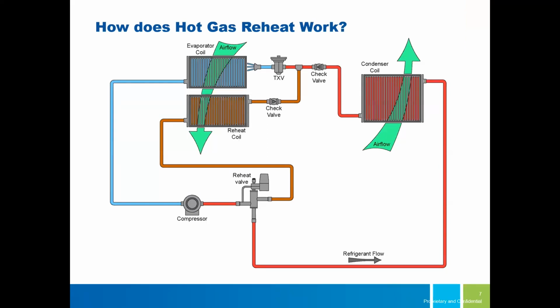For smaller package units, there are different styles of reheat. They have on/off, so it's basically one size coil. Generally speaking, for smaller package units, you see air coming in reheat mode usually off of 70-degree neutral air, or some type of dry neutral air that comes off of it in some way, shape, or form. And I could be wrong. We're getting into the applications realm, which is a little out of my expertise.